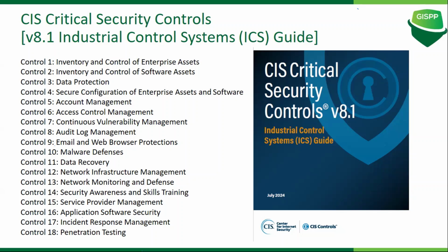With a data diode, the data that is getting inside the ICS is on a totally different channel from the data going out. It is two separate pipes. One pipe in the data diode takes data inside, and one pipe takes data outside. So if you perform deep packet inspection for the data coming in, you can provide fewer checks. You can install more checks on the devices that are sending the data to that data diode. So the availability is not hampered.